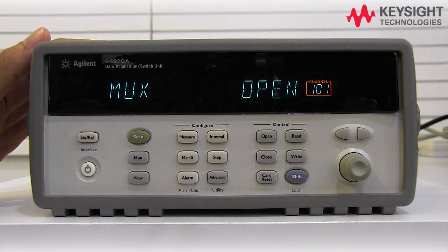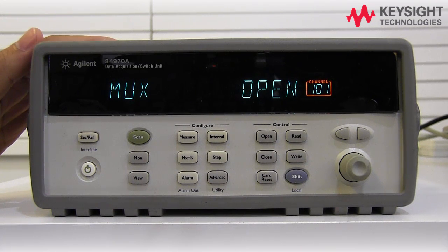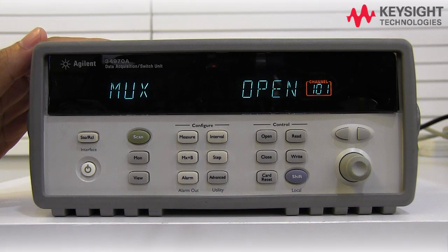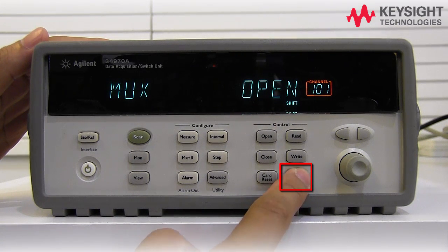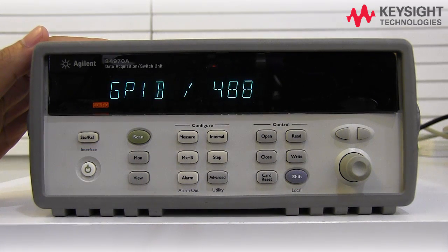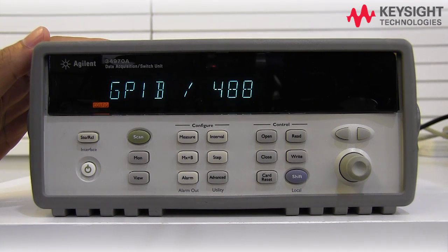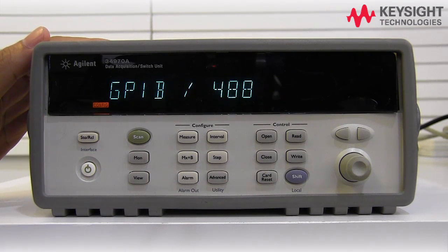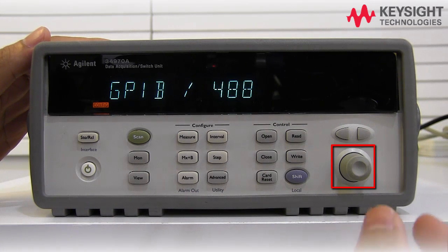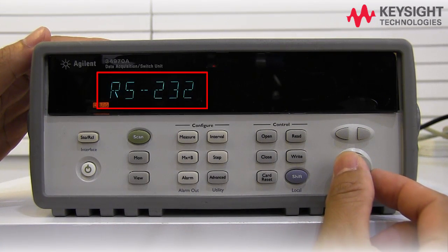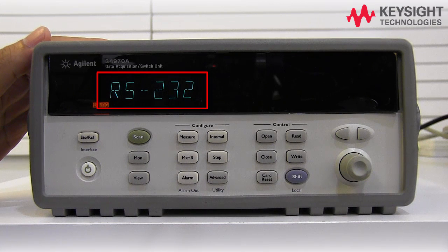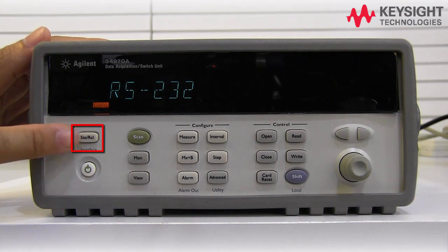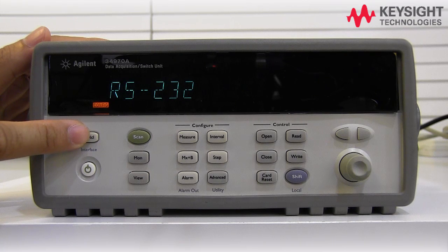we need to make sure the setting for RS232 on 34970 instrument is correct. To do this, we need to press Shift and then go to interface. If your default interface is not RS232, then we need to turn the knob to change the interface setting and press this button to save the RS232 setting.